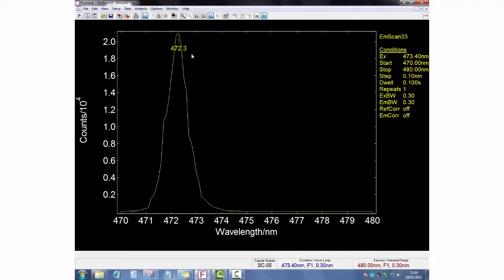If the position of this peak is out of specification, then we do a similar process to what we did with the excitation monochromator. We go to Setup, User Calibration Setup, and calibrate emission monochromator, and we input the measured peak position and the desired peak position, which is 473.4 nanometers.